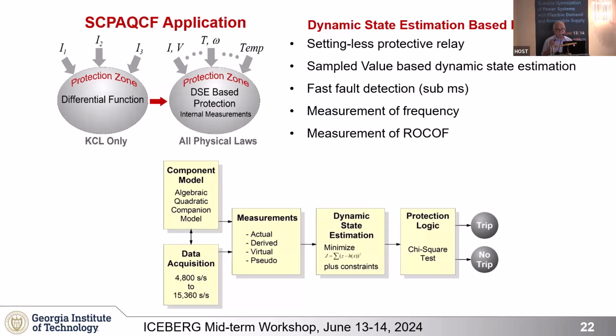That can be done very easily with dynamic state estimation. If there is consistency between the measurements and the model of the protection zone, then we can assume there is nothing wrong with the device, so we let it operate. If there is a fault in the system, then we need to trip that protection zone. Of course, we need to keep in mind that if somebody attacks the relays through cyber means, they can generate wrong data and the relay can misoperate. But that's true whether we're using this method for protection or any other protection method—if somebody attacks the data, we have a problem.